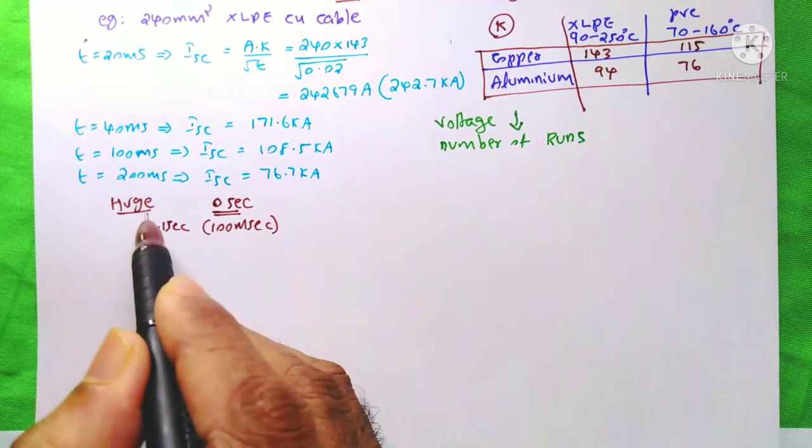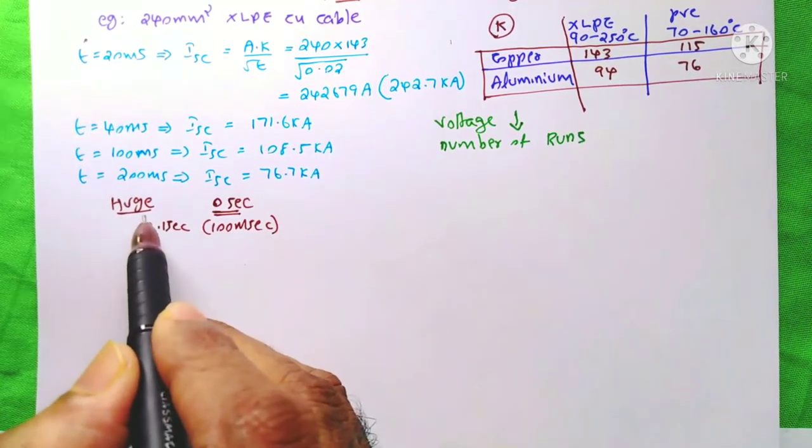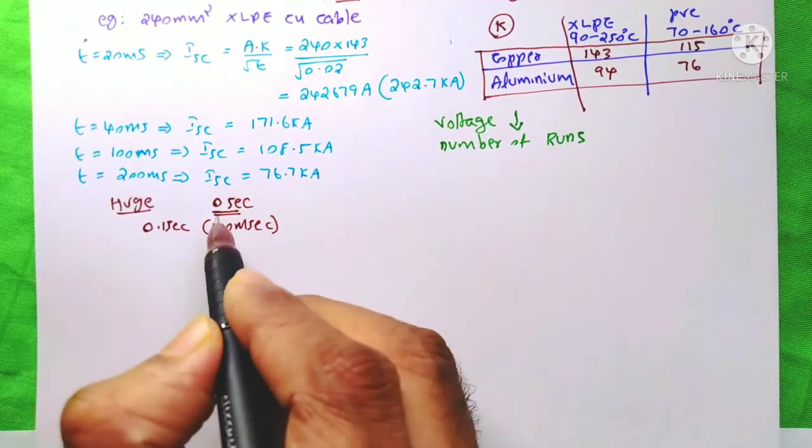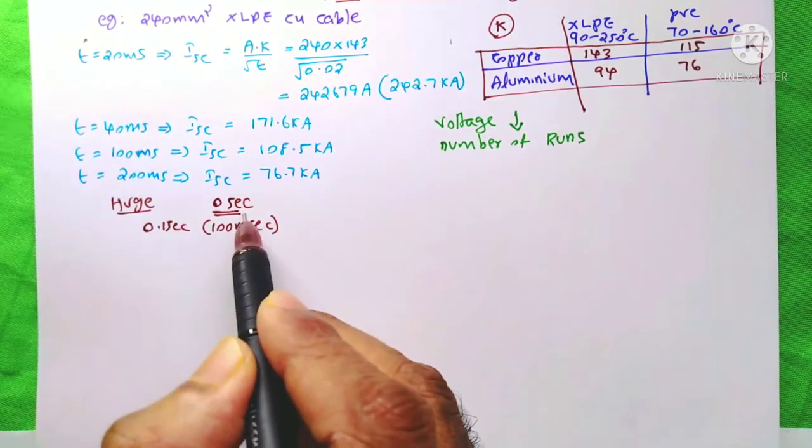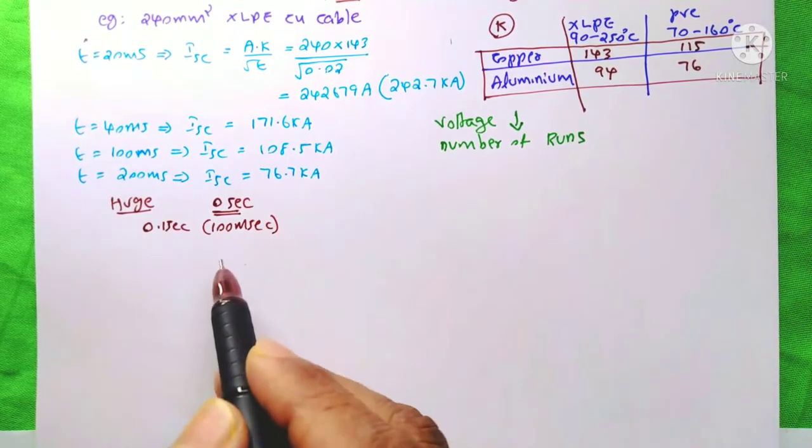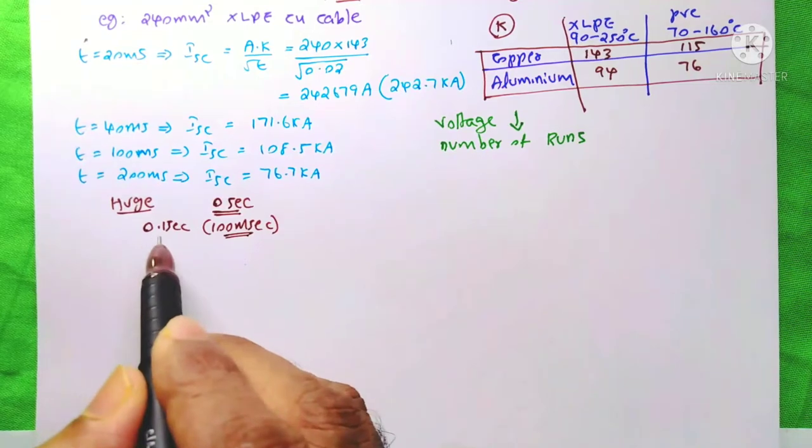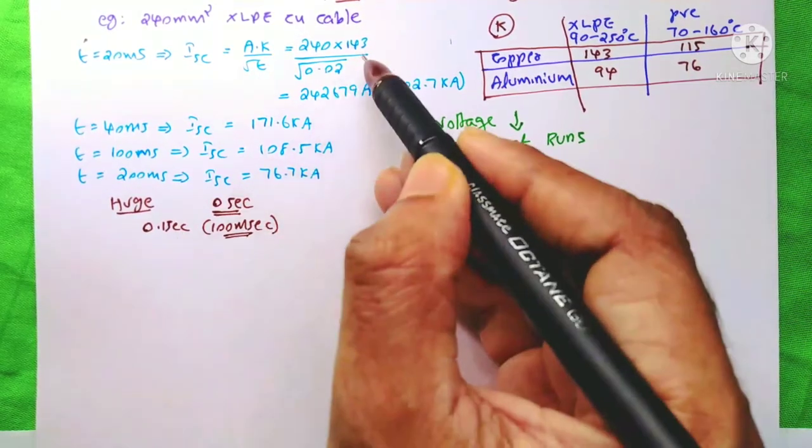When huge short circuit appears on a system, our circuit breaker will trip instantaneously without any time delay. But I recommend you to always take 100 ms, that means 0.1 seconds for this calculation.